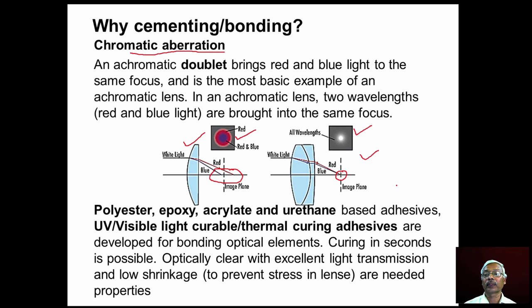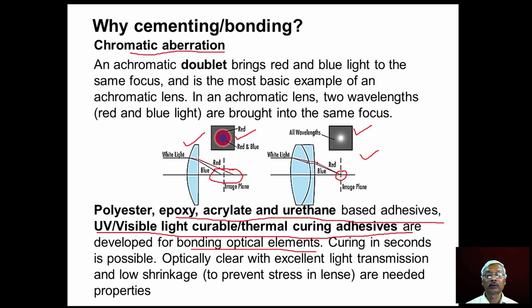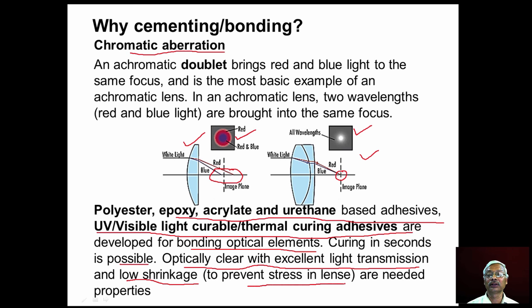Different adhesives are available: polyester, epoxy, acrylate, and urethane-based adhesives. Ultraviolet, visible-light-curable, and thermal-curing adhesives are also available for bonding optical elements. Curing is possible in a few seconds. The cement should be optically clear with excellent light transmission capability, and shrinkage must be very low to prevent stresses in the lenses.